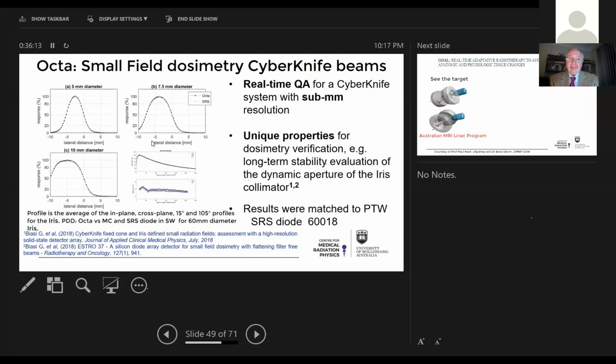And plus, these detectors are tissue equivalent. It's no problem. You can see the comparison of the depth dose curve for this detector as a function, compared with Monte Carlo simulation. Particularly, it was done for a 60 millimeter diameter opening of the iris collimator. So we introduced a new domain of small field dosimetry with Magic Plate. We call them monolithic Magic Plate. And currently we are developing a detector 75 by 75 millimeter with 987 channels, with resolution 1 millimeter in the center and 2 millimeter outside. So it's a beautiful detector which is currently under investigation in MRI LINAC.